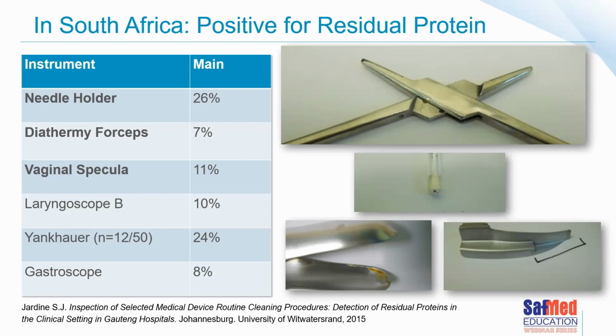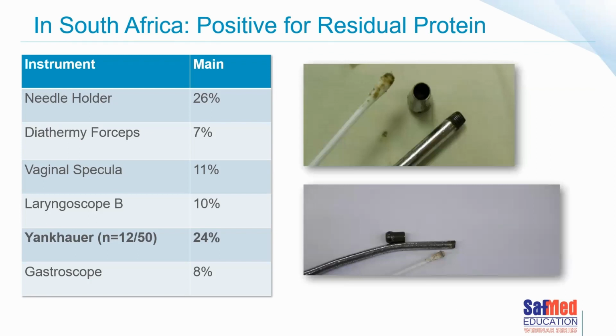If a device tests positive for residual protein, it means it was not properly cleaned. And as we all know, a device that hasn't been properly cleaned can never be disinfected or sterilized for that matter. Needle holders, diathermy forceps, and vaginal speculums can all be processed either manually, in an automated washer disinfector, or in an ultrasonic cleaner. Laryngoscope blades are a little bit trickier because they can generally only be cleaned manually, depending on the instructions for use. Most of the blades need a manual clean and can't go in a washer or an ultrasonic cleaner at all.